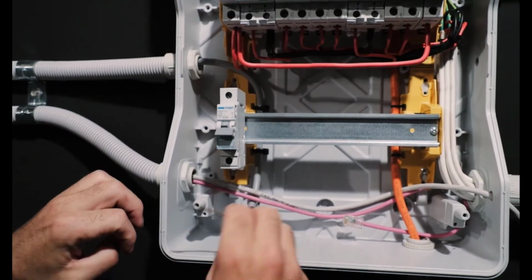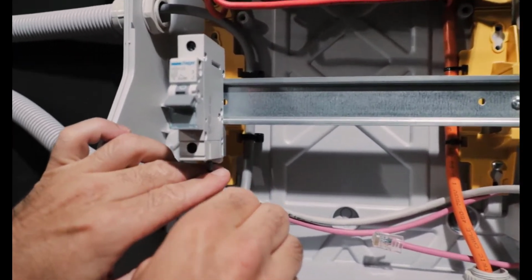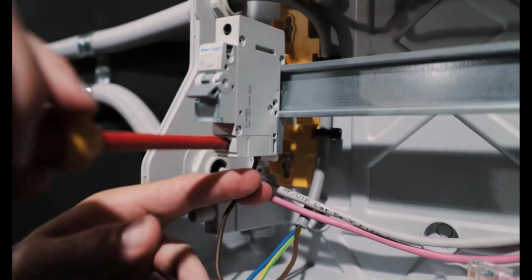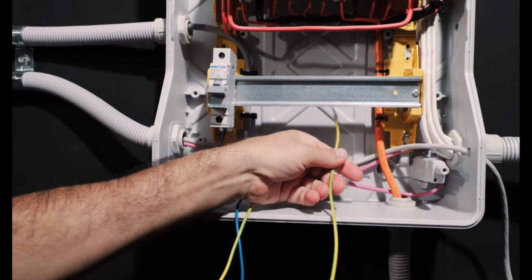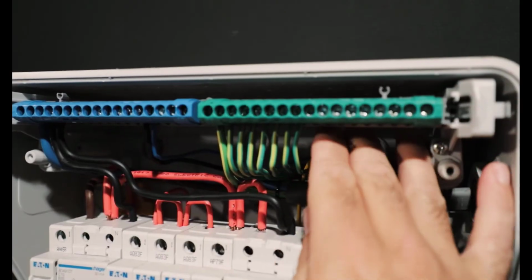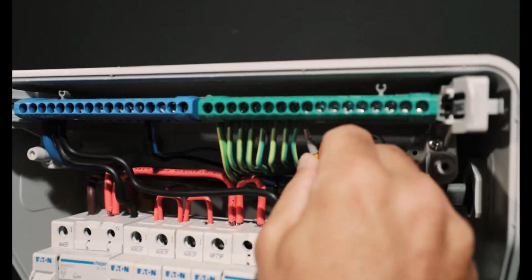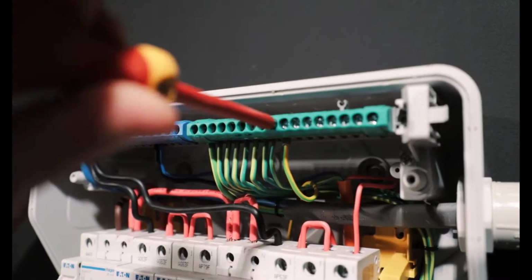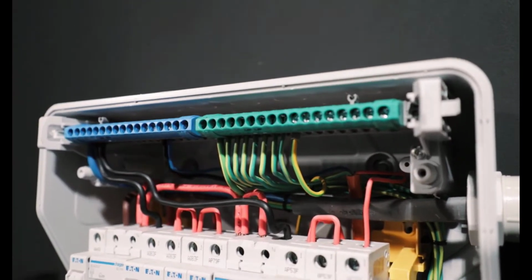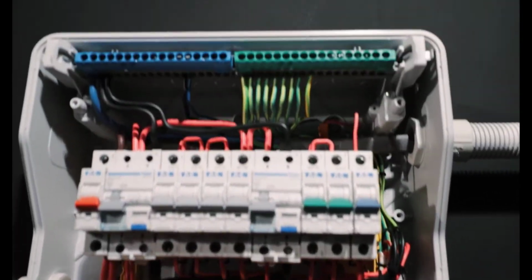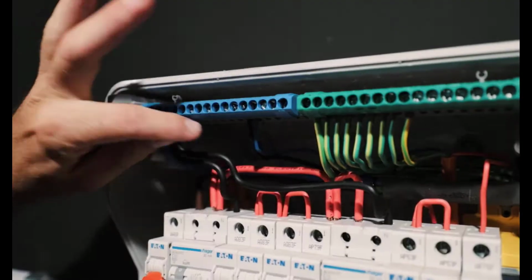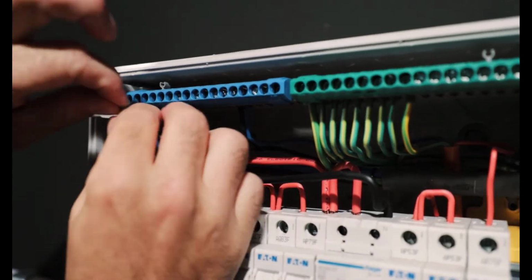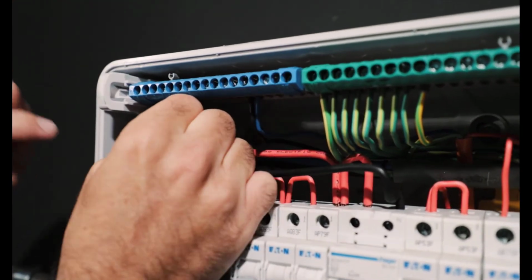So the main difference is there are two setups. We have grid measurement and consumption measurement. The reason we have the two is that consumption measurement is purely looking at the power going to the loads. It's the most accurate form of measurement to look at the actual domestic consumption. The sonnen system will then calculate what's going on through the grid connection.